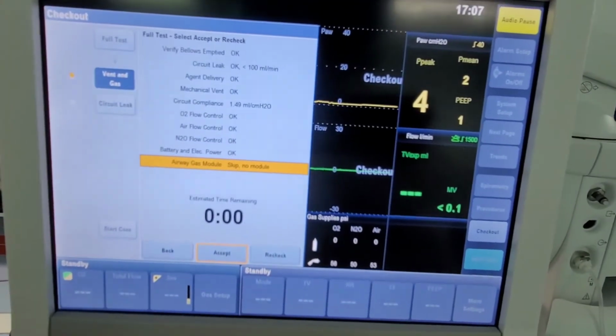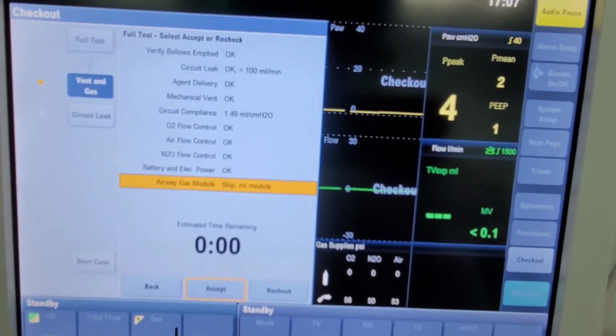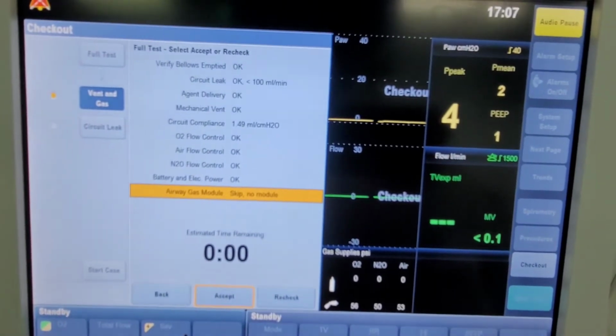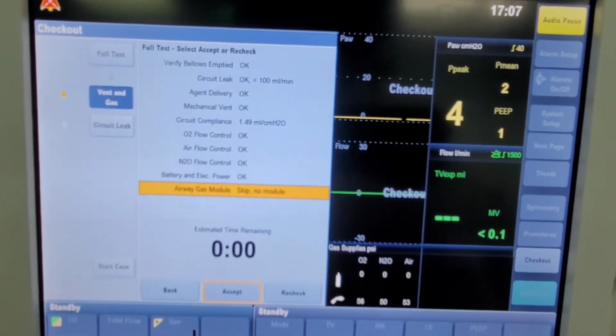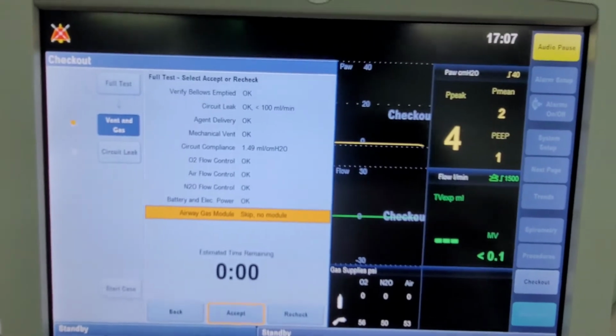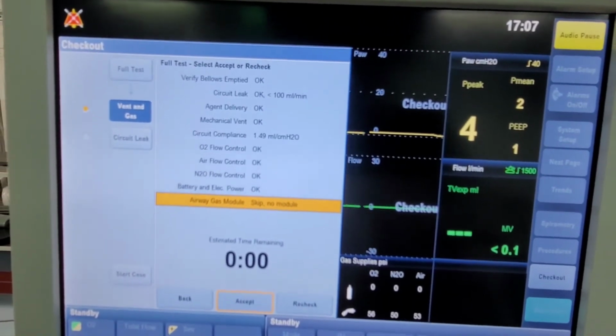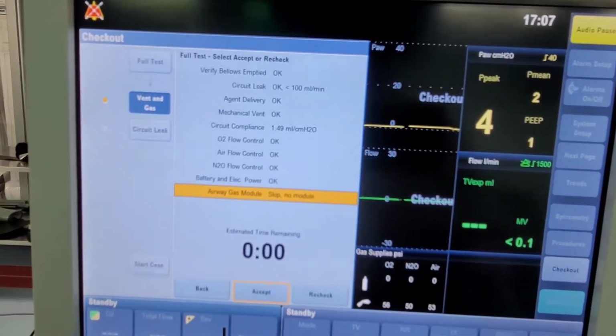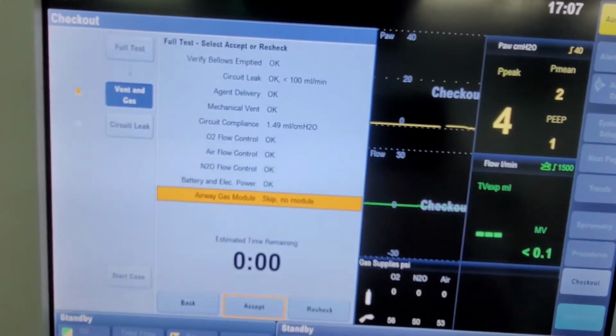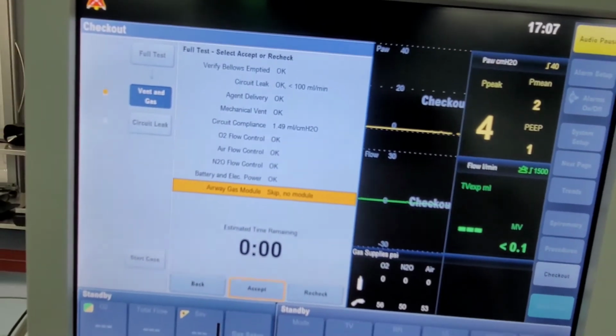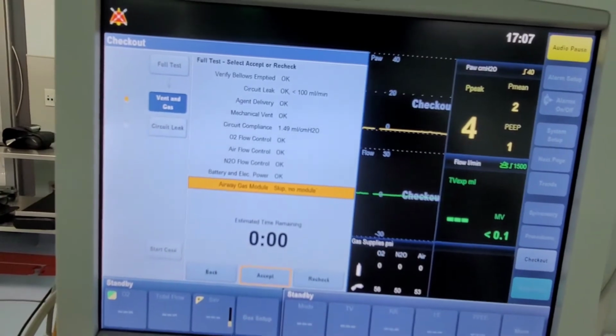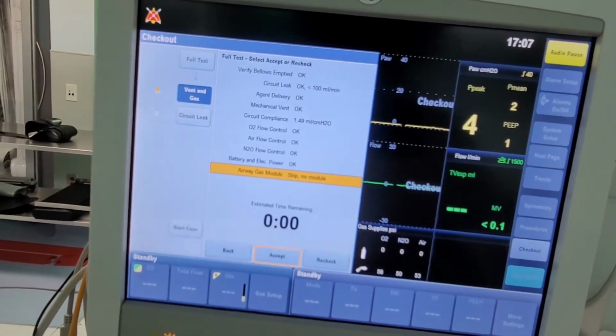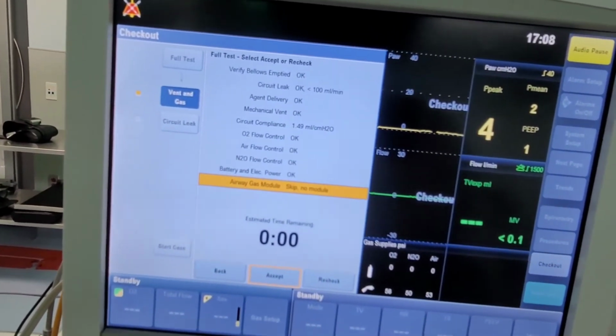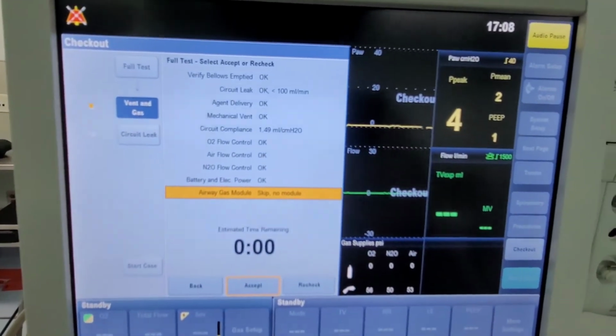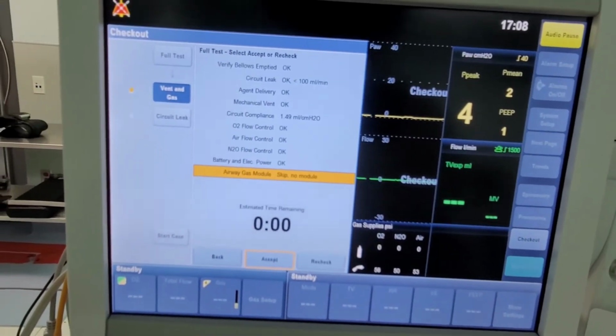Alright, as you can see here, it passed everything. The circuit leak was at 100 mL per minute, which is perfect. If it's anything bigger than that, it's usually up to about 250 or 260 and it's barely passing. That means there's a minor leak somewhere that we need to troubleshoot down the road. But it's still acceptable and can go through the case without any issues.